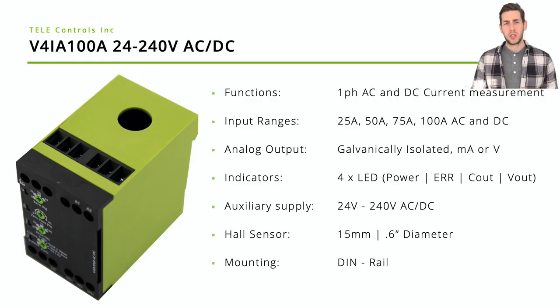For the measuring range, we have the opportunity to also offset our zero starting point. So if you think of a linear current increase, you could, for example, make sure you ignore the little ground noise that appears from, say, 0 to 0.5 amps.